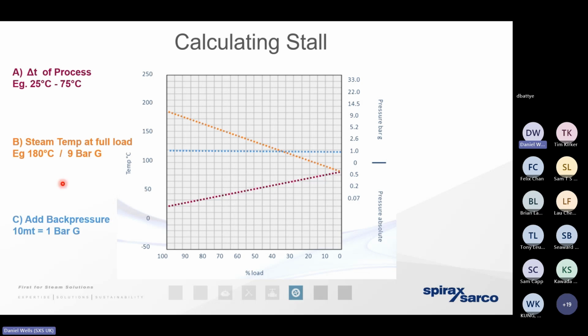We then plot the back pressure. It's really the lift that is present within the condensate infrastructure. Useful rule of thumb to bear in mind is that 1 bar gauge steam pressure can lift a column of condensate vertically 10 meters. So if we've got a 10-meter lift, we could express that as being a 1 bar gauge back pressure. So where the two lines converge, that tells us that this is the point where we don't have enough motive energy to get the condensate out of the heat exchanger. That's a stall point of 41% load.